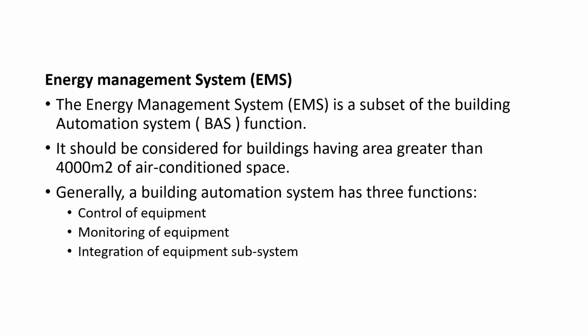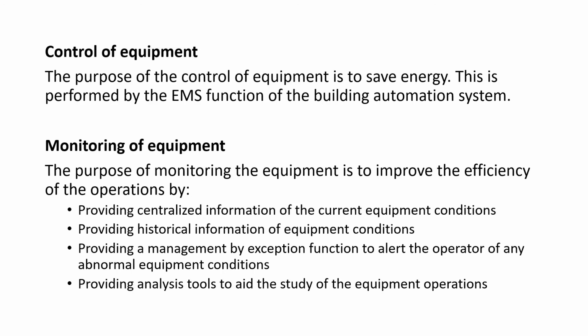Energy Management System (EMS). The Energy Management System (EMS) is a subset of the Building Automation System (BAS) function. It should be considered for buildings having an area greater than 4,000 m² of air-conditioned space. Generally, a building automation system has three functions, which are control of equipment, monitoring of equipment, and integration of equipment subsystems. So for control of equipment, the purpose is to save energy. This is performed by the EMS function of the building automation system. For monitoring of equipment, the purpose is to improve the efficiency of the operations by providing centralized information of the current equipment conditions, providing historical information of equipment conditions, providing a management by exception function to alert the operator of any abnormal equipment conditions, and providing analysis tools to aid the study of the equipment operations.